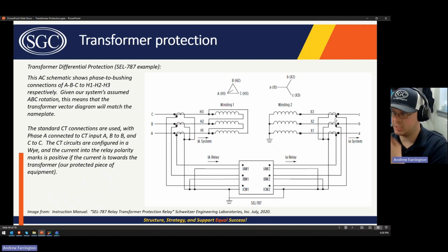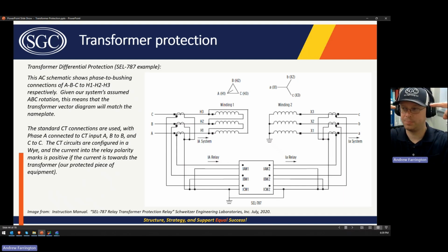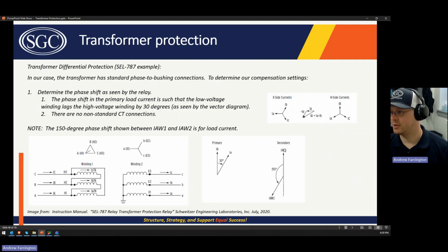Because of the way the CTs are connected, this polarity connection here goes, they're pointing in opposite directions. They're pointing towards the protected piece of equipment, which is what we want. But when there's load current, the current is going into the non-polarity side of this CT. So what's actually going into the relay input is the inverse of the current that's going into the transformer. So what the relay is actually seeing is this.